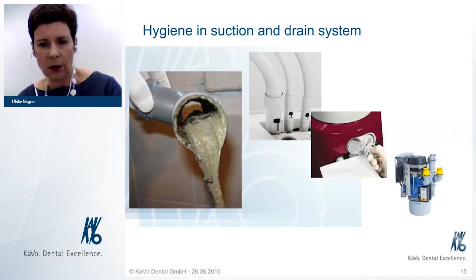In maintaining the functionality of the suction system and providing the hygiene functionality, KaVo units provide an integrated flushing program. It is called Hydroclean, and this flushing program should be activated after each patient with only adding cold water into the suction lines inside the unit, flushing the drains, the separation, the valves, and so on. In addition to that, for the hygiene maintenance, the suction system requires disinfection, and this we provide by a disinfectant called Dekaseptol gel.